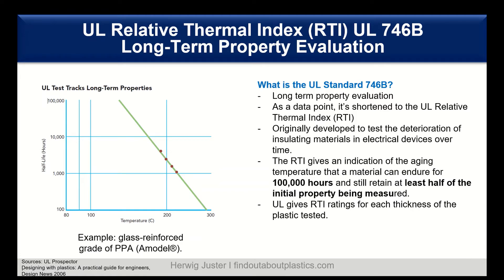So what is the UL standard 746B in detail? It is for long-term property evaluation — as a data point it is shortened to the UL Relative Thermal Index, RTI — and it was originally developed to test the deterioration of insulating materials in electrical devices over time, so mainly for the electrical industry. RTI gives an indication of the aging temperature that the material can endure for 100,000 hours and still retain at least 50%, or half, of the initial property being measured.